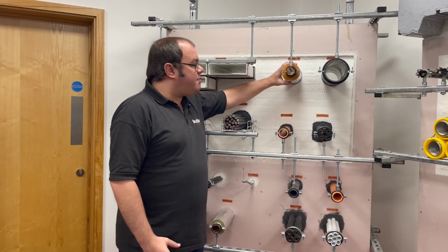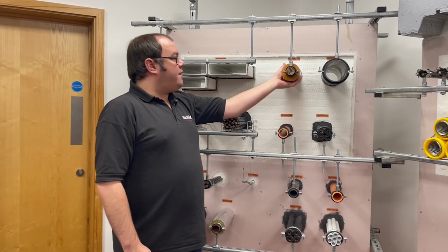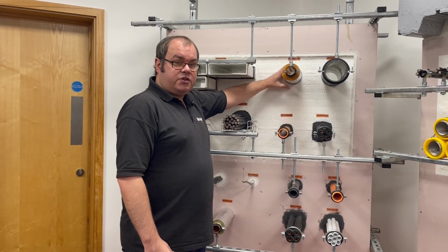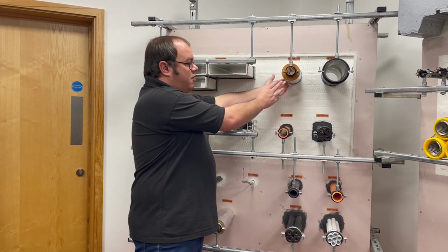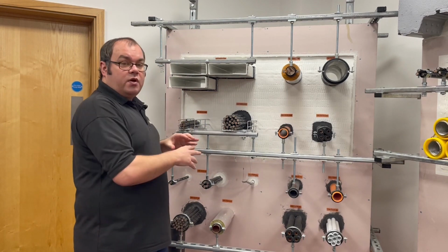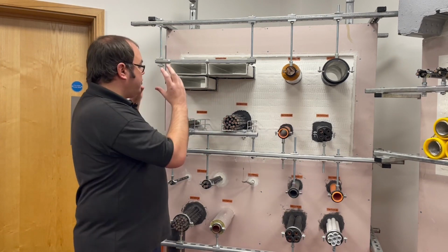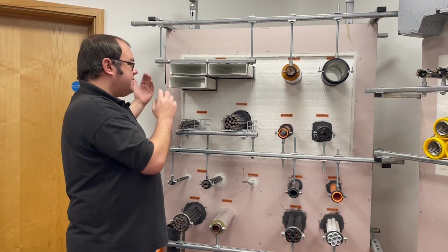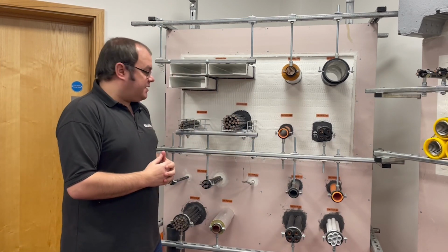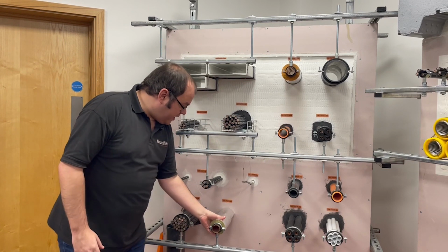penetration. What you might also have is what's called local sustained, so LS. So that's where the insulation will go right through the penetration, but then it will stop at a prescribed distance. So for example, with our shaft wall details where we did some installations from one side only with the steel pipes, we pushed some rock fibre insulation through from one side, a prescribed distance that extends both sides of the wall and then stops. So that's very good for some uninsulated metal pipe details to achieve that insulation fire resistant rating.